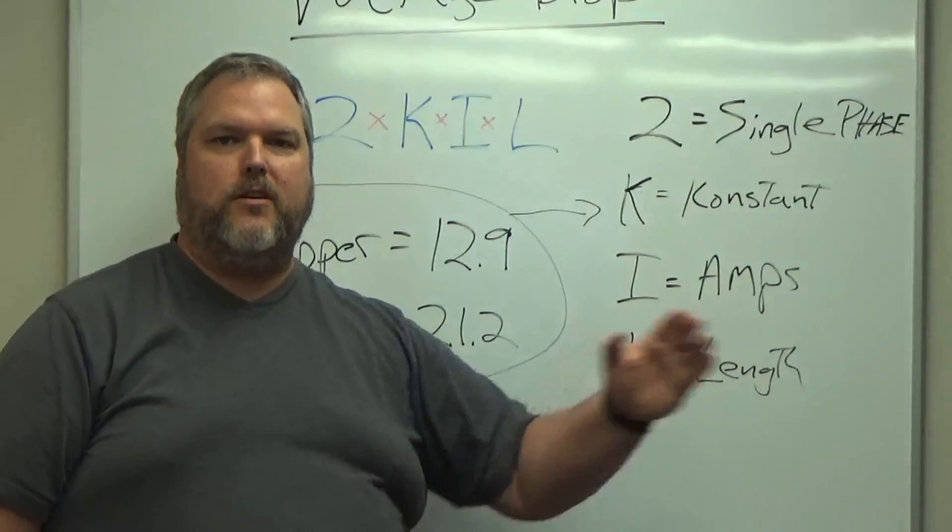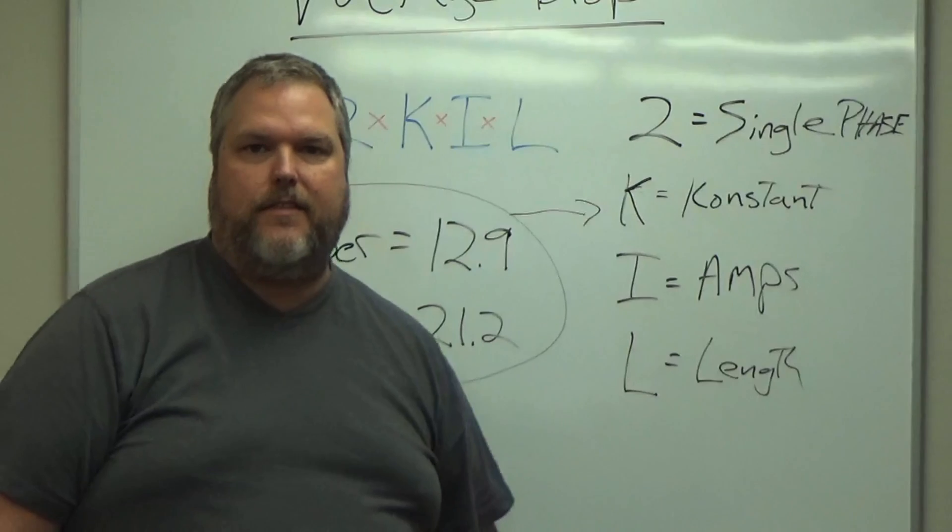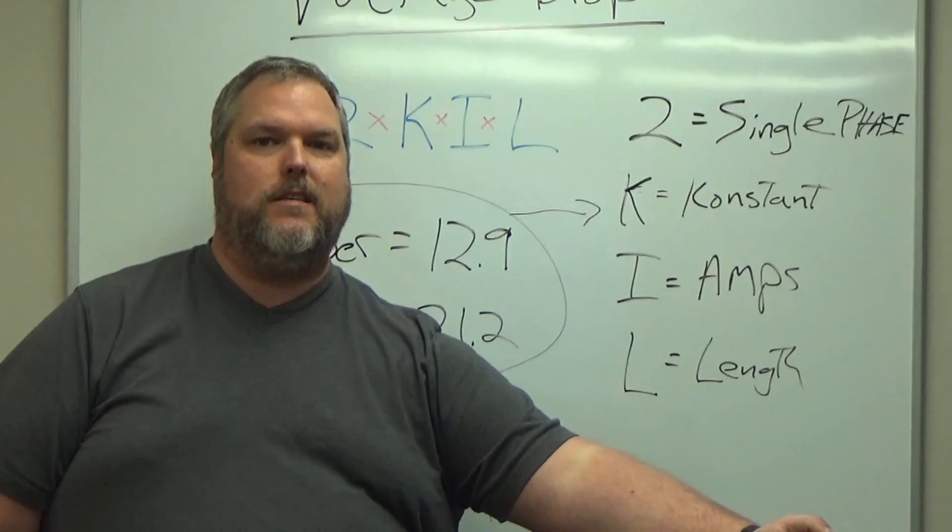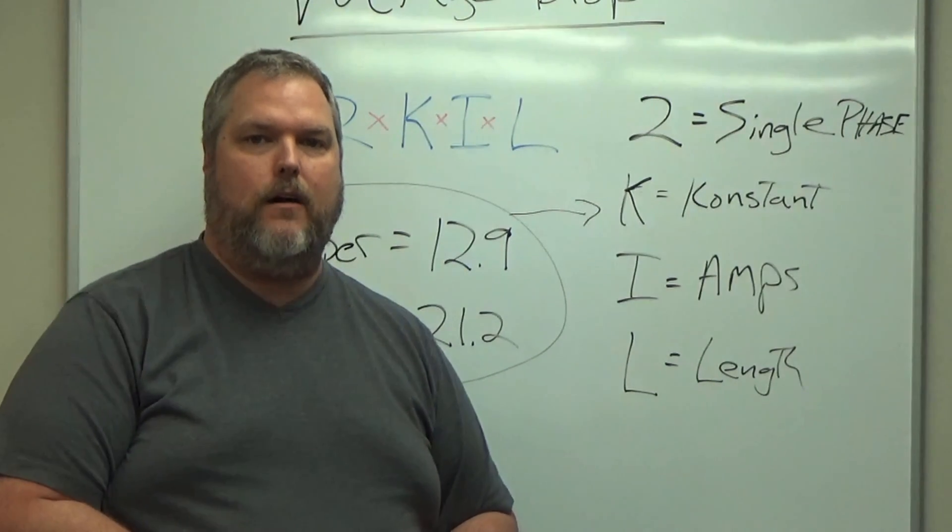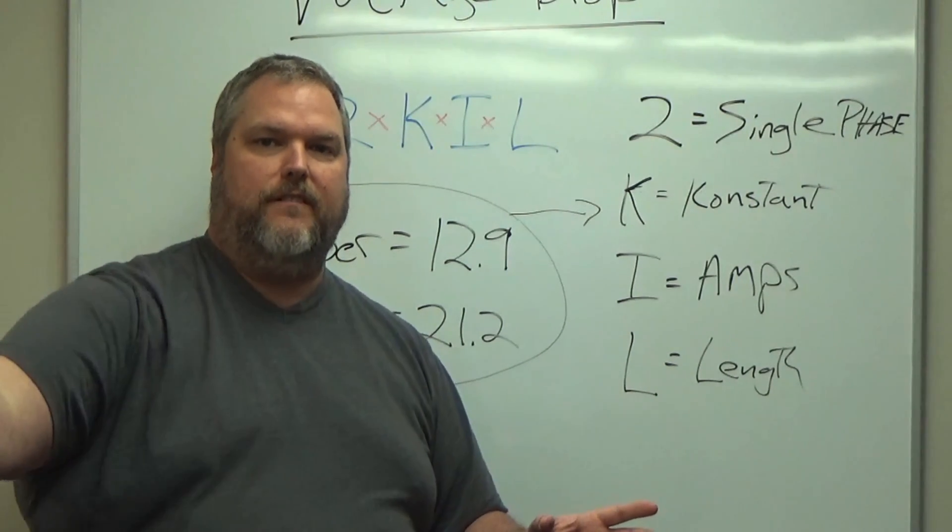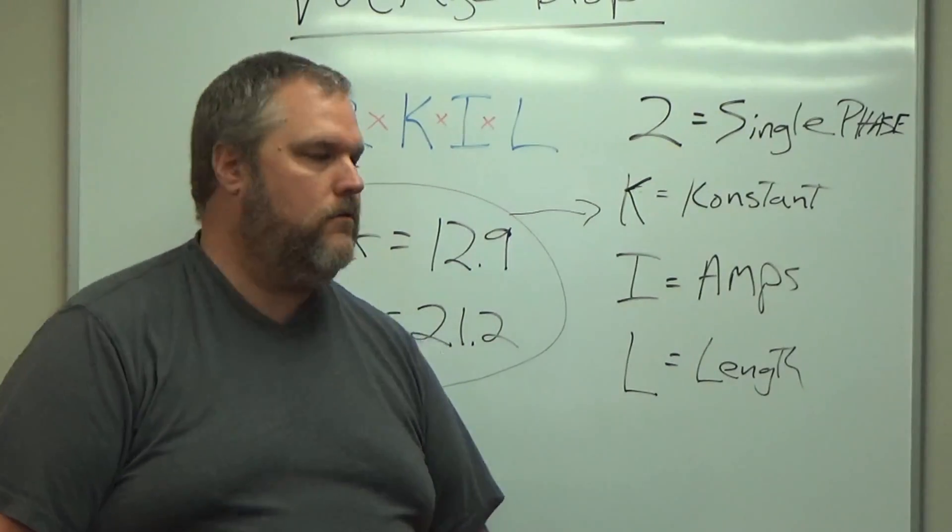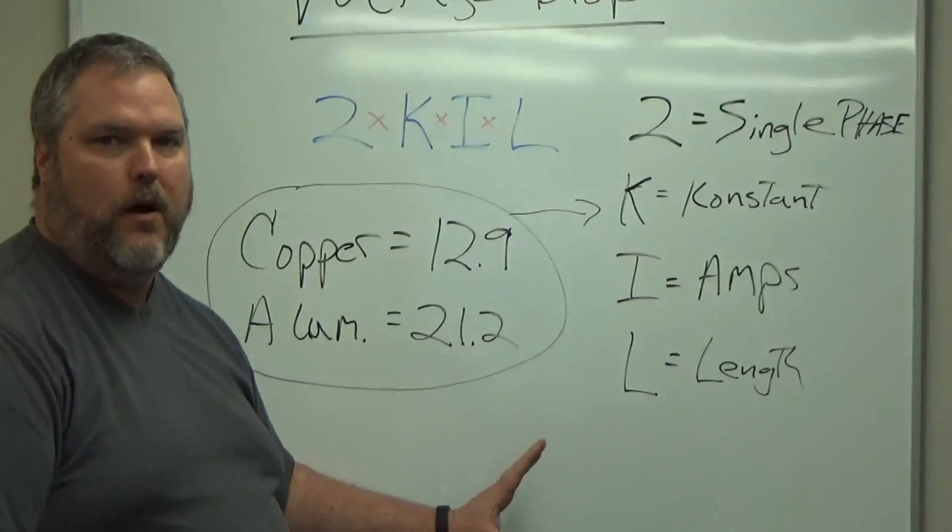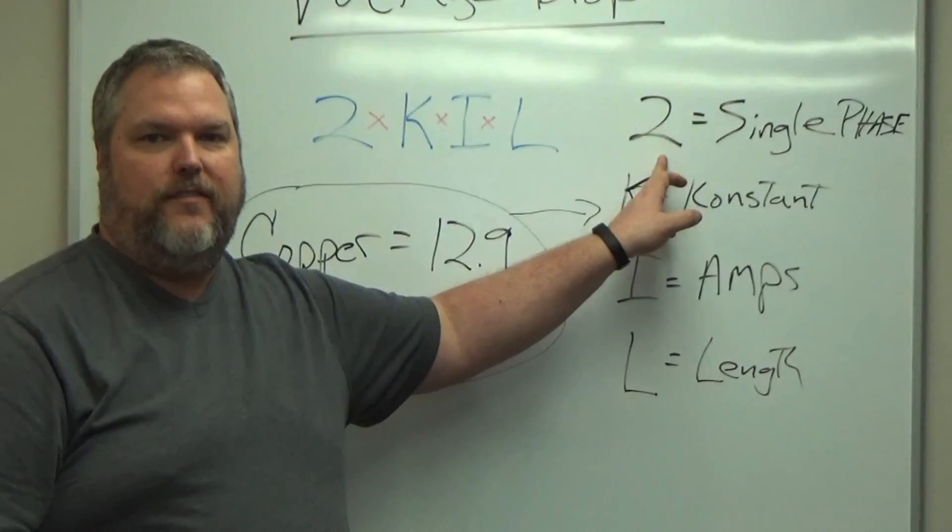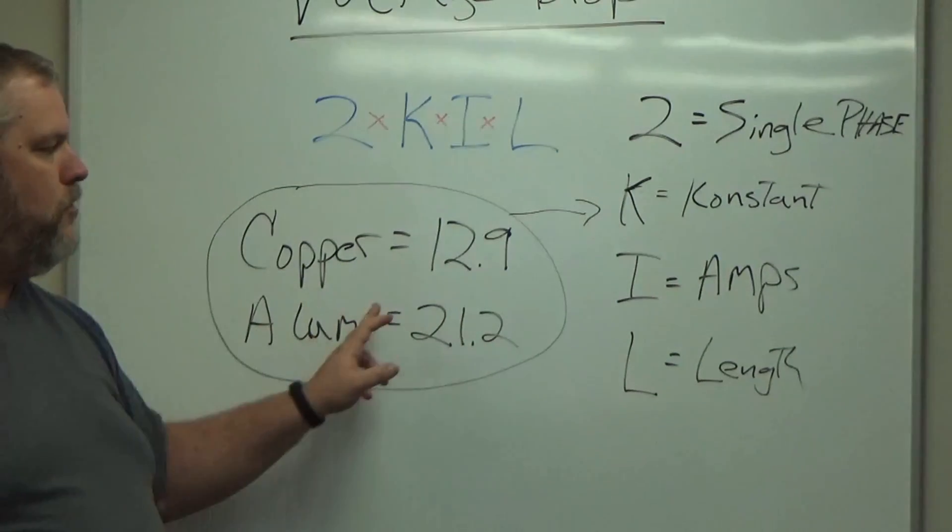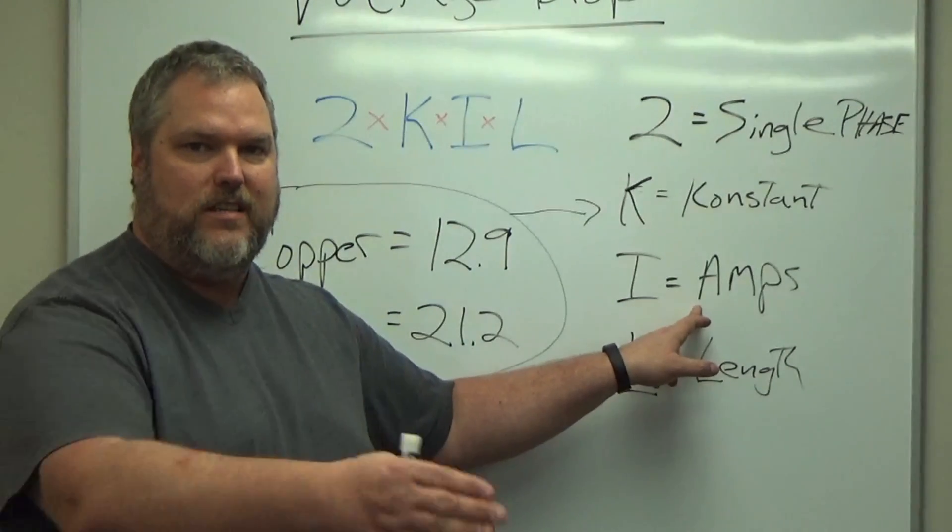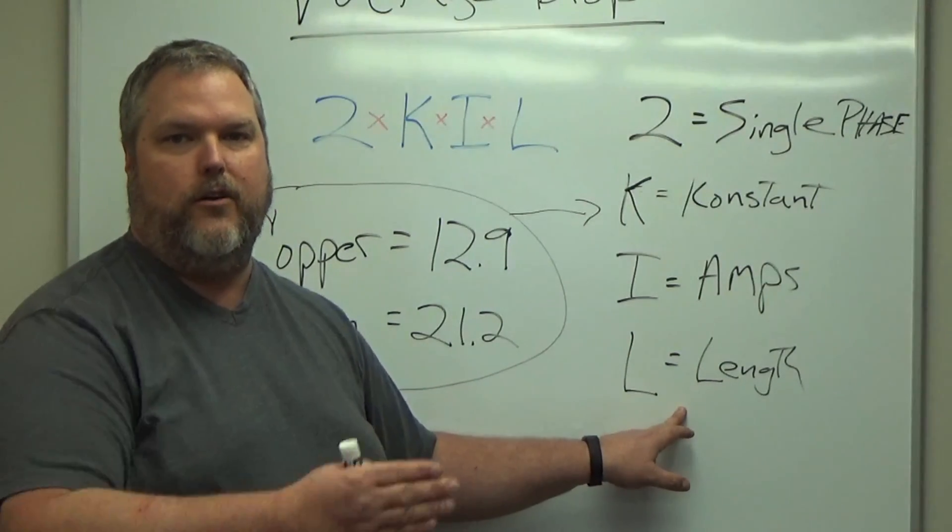Now, the amps are going to be what we need. The length is going to be from the breaker that's feeding this location to its end location. So if I have a panel in a main house and I've got to run to another panel in a shed, it's from where I'm going to feed that breaker to feed the shed. We're going to use a shed as an example. We know that 2 stands for single phase, K stands for the constant for copper or aluminum wire, and these are the two numbers we're going to use. Amps is going to be the amperage we're trying to receive at that location, and the length is how far from breaker to breaker we're going to be going.